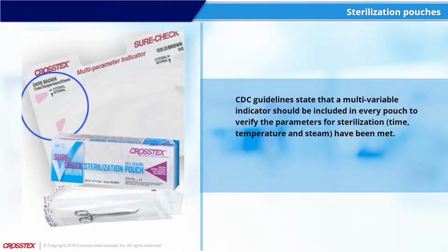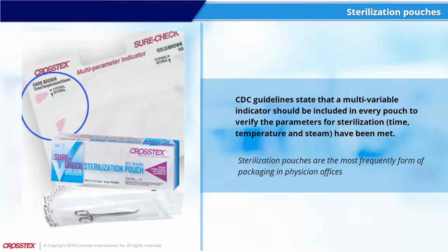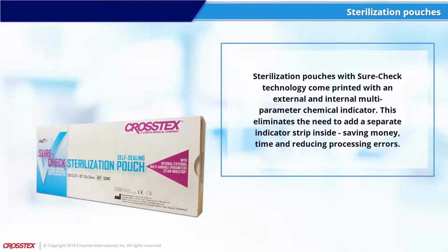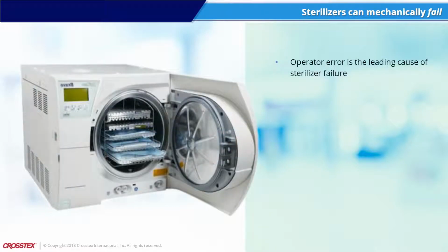Sterilization pouches are the most frequently used form of packaging in physician offices. CDC guidelines state that a multivariable indicator should be included in every pouch to verify the parameters for sterilization, time, temperature, and steam have been met. Sterilization pouches with SureCheck technology come printed with an external and internal multi-parameter chemical indicator. This eliminates the need to add a separate indicator strip inside, saving money, time, and reducing processing errors.